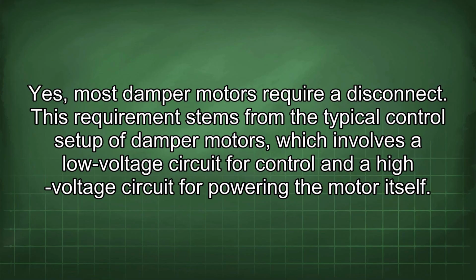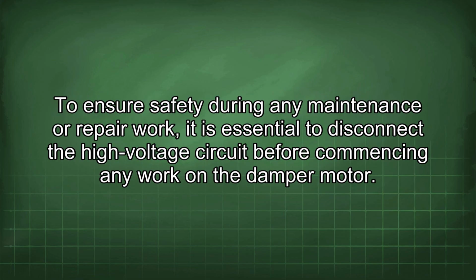Yes, most damper motors require a disconnect. This requirement stems from the typical control setup of damper motors, which involves a low voltage circuit for control and a high voltage circuit for powering the motor itself. To ensure safety during any maintenance or repair work, it is essential to disconnect the high voltage circuit before commencing any work on the damper motor.